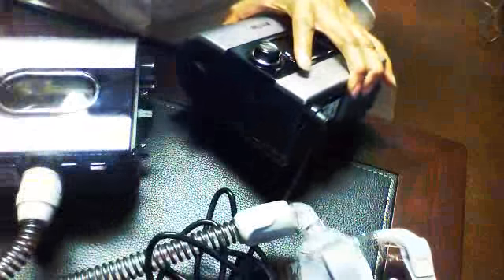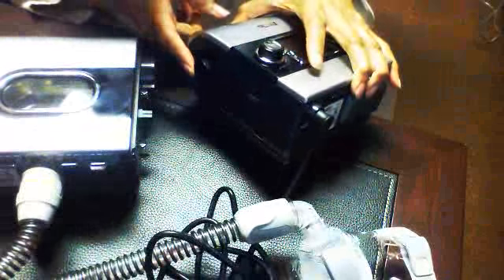Now we will connect the humidifier back to the CPAP unit. The CPAP unit has a small tubing here, and there's a larger plastic tubing opening on the humidifier. The small tube goes inside the large tube, and then you just push, and when you hear a click, they're snug together.